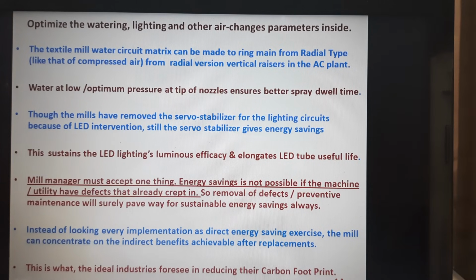The water needs to be operated at a lower optimum pressure only. Then comes the LED lighting. Almost 99 out of 100 mills have changed over to LED lighting. Excellent. But they must maintain the luminous efficacy of the LEDs and elongate the useful life of the LED tube lights. Definitely a mill has a lot of spare servo stabilizers, or if you don't have one, try to buy a new servo stabilizer, especially for your MLSB, and this gives an energy saving of 3 to 5%. Definitely mills have done that and they have shared their inputs with us.